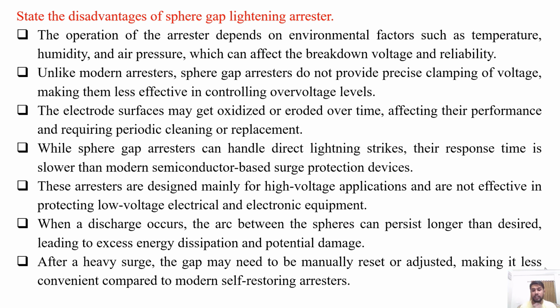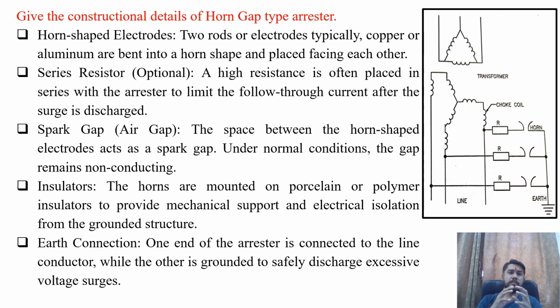After a heavy surge, the gap may need to be manually reset or adjusted, making it less convenient compared to modern self-restoring arresters. So these are several disadvantages of sphere gap lightning arrestor. Give the constructional details of horn type gap arrestor. So in the figure you can see the horn type lightning arrestor. In this, a series resistor is connected and a choke coil is placed with the transformer in all three phases. The transformer is connected delta star. So horn shaped electrodes means two electrodes or rods, typically made up of copper or aluminum, are bent in a horn shape and placed facing each other like this.